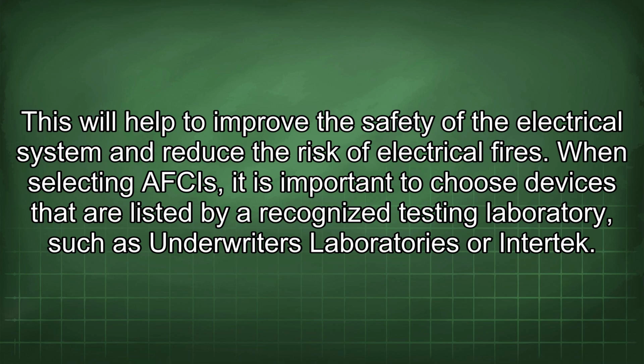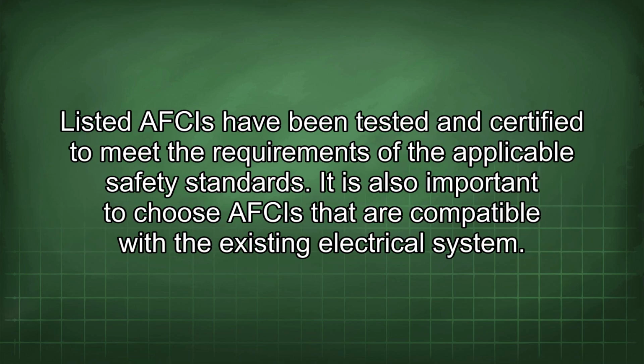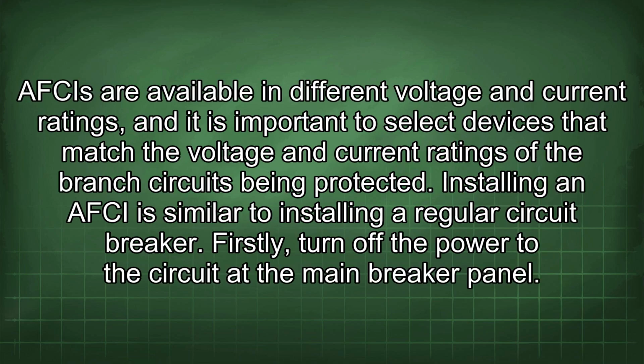When selecting AFCIs, it is important to choose devices that are listed by a recognized testing laboratory such as Underwriters Laboratories or Intertek. Listed AFCIs have been tested and certified to meet the requirements of the applicable safety standards. It is also important to choose AFCIs that are compatible with the existing electrical system. AFCIs are available in different voltage and current ratings, and it is important to select devices that match the voltage and current ratings of the branch circuits being protected.